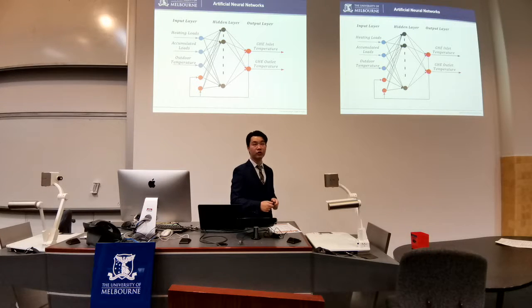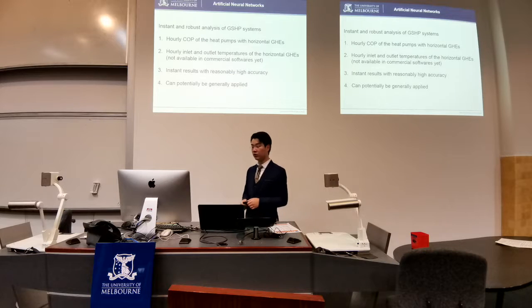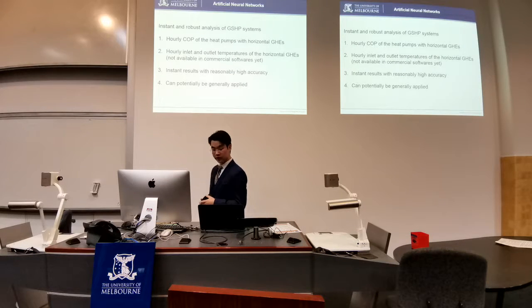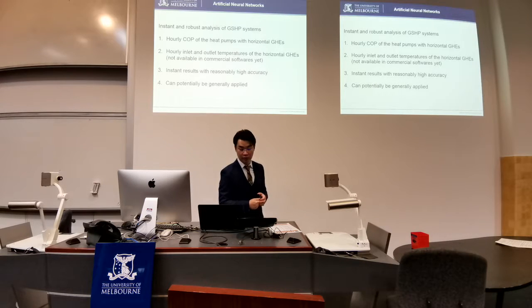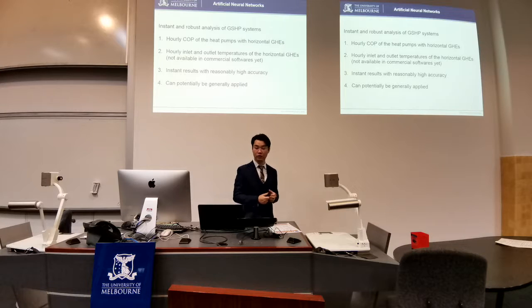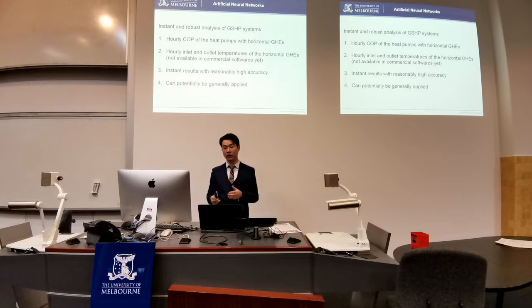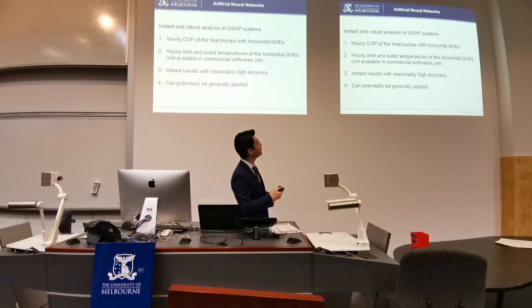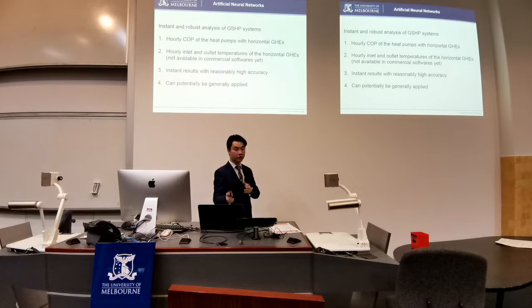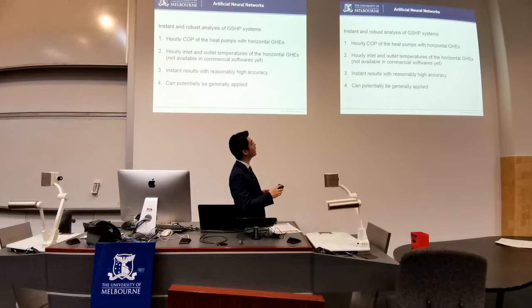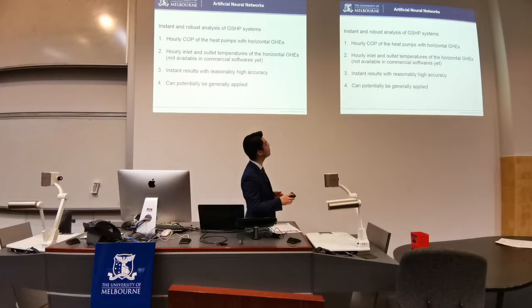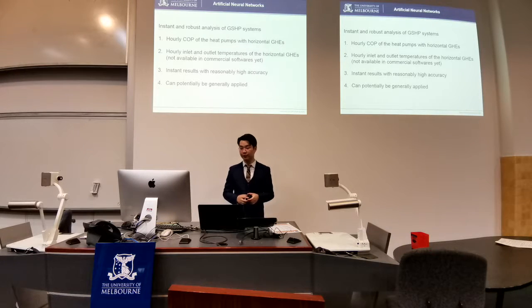Using these artificial neural networks, we can get instant and robust analysis of ground source heat pump systems, including the hourly COP of heat pumps with ground heat exchangers, and the hourly inlet and outlet temperature of horizontal ground heat exchangers. This feature isn't currently available in any commercial software yet. We've seen that we can get instant results with reasonably high accuracy, and it could potentially be applied much more generally.